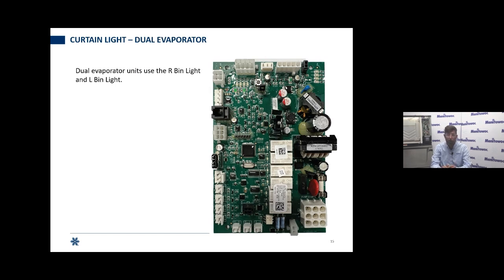Now, the dual evaporator machines, so the IF 1400, 1800, 2100, as well as the IT 1830, they utilize two evaporators. So we have to use two dampers. Dual evaporator machines use ice dampers. Same theory. It's a magnet inside of a flapper instead of a curtain, communicating with a magnetic bin switch, a reed switch in there. Now, this one gets a little confusing because we call out our bin, but think of it from your perspective. The light on the left will correspond to the left-hand damper, and the light on the right will correspond to the right-hand damper. So ignore the label. Look at where the lights are. Left-hand side, left damper, you flap it, light goes off and back on. Same would be true with the right.